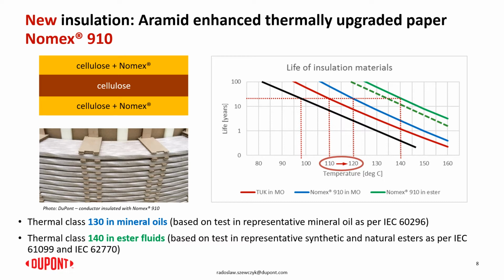One new type of insulation is what we call Aramid enhanced thermally upgraded paper. We call it Nomex 910. It might be sometimes confusing with other grades of Nomex, which are 100% Aramid papers or pressboards, and they are normally rated for the class 180 degrees Celsius in the liquid immersed transformers. The Nomex 910 is lower thermal class because it's basically the thermally upgraded paper with just a small proportion of Nomex added to it for improving the performance after long-term exposure to the temperature.